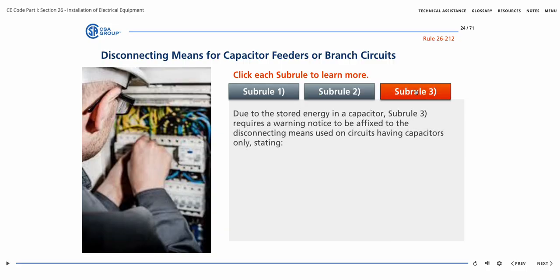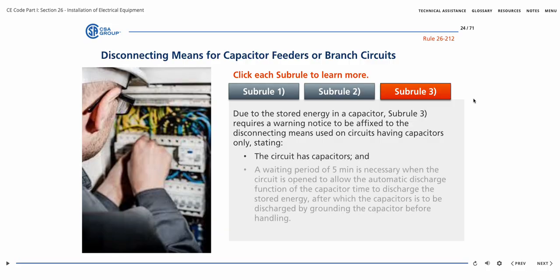Due to the stored energy in a capacitor, Sub-Rule 3 requires a warning notice to be affixed to the disconnecting means used on circuits having capacitors only, stating, "The circuit has capacitors and a waiting period of 5 minutes is necessary when the circuit is open to allow the automatic discharge function of the capacitor time to discharge the stored energy, after which the capacitor is to be discharged by grounding the capacitor before handling."